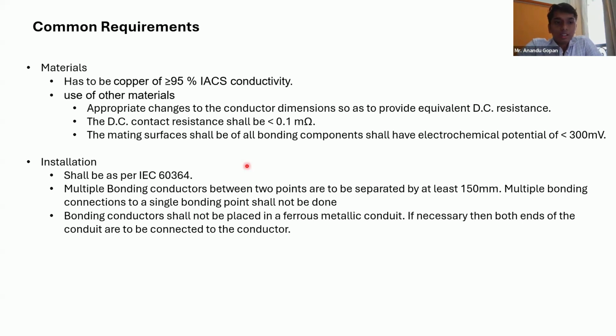And as I've repeated again, this installation must be as per IS 732, because no matter what type of telecommunication requirement you have, what is important is safety. Only after that comes the requirement for telecommunication networks. In the upcoming slides, I will tell you that you have to connect this part, and there will be multiple connections. It is preferable that these connections are at least 150 millimeters apart. Basically, if you are working in that region, you will not disconnect one of these conductors during maintenance. To avoid that, you should have at least 150 mm. And in places where you cannot have it, it's better to follow this 150 mm minimum requirement.